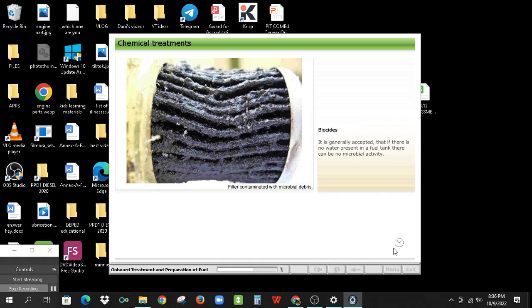It is generally accepted that if there is no water present in a fuel tank, there can be no microbial activity. You should therefore make sure that water is drained from fuel tanks regularly. Watch out for the smell of rotten eggs, hydrogen sulfide gas from the tanks, which will give some indication of the problem. When microbial contamination does occur, you will need to use biocides to kill off and control recurrence of the bacterial colonies. There are many different biocides available, and most are about 90% effective, so repeat treatment is usually necessary.